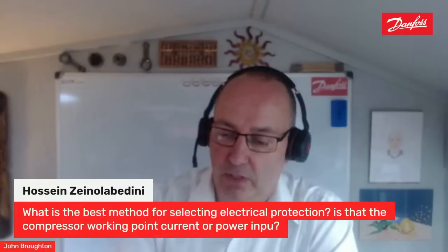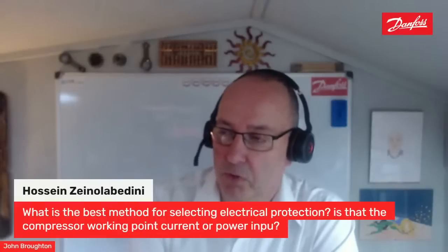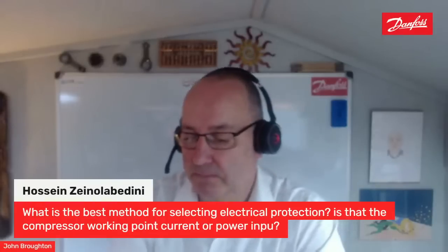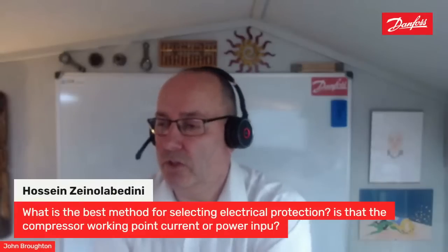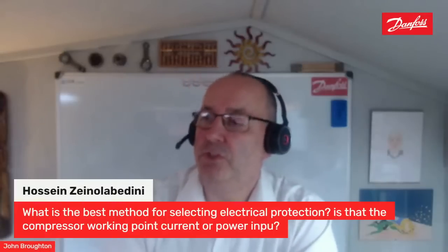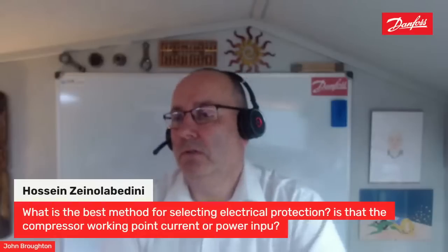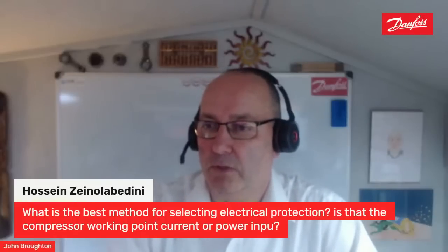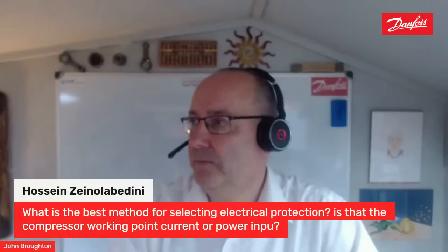Because generally, if you've got a low temperature compressor, the motor is smaller. If you've got a high back pressure compressor, the motor's larger to cope with that increase in suction pressure and the required torque in the motor to actually run. So hope that answers that one, Hosin.